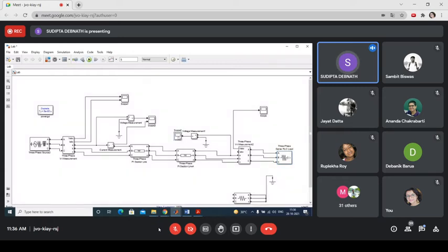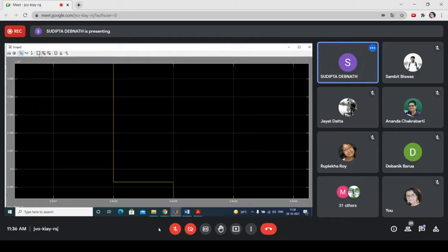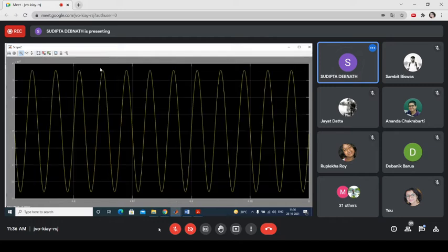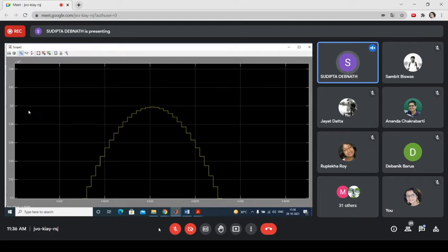What is the receiving end voltage? See, the receiving end voltage is almost 360 kV. So under unloaded condition, the receiving end voltage is 360 kV, which is much more than the sending end voltage, which is 326.6 kV.